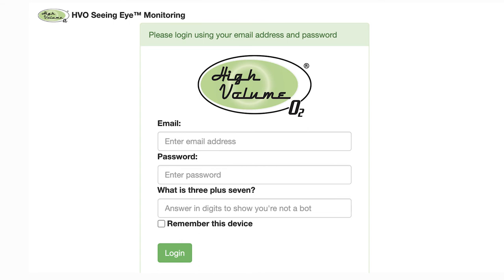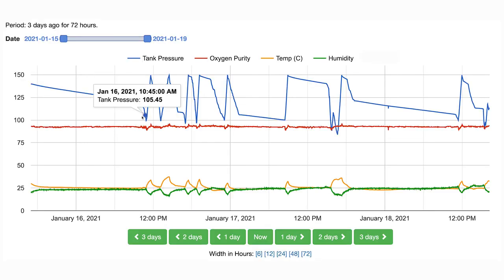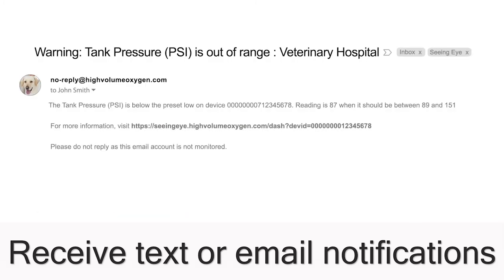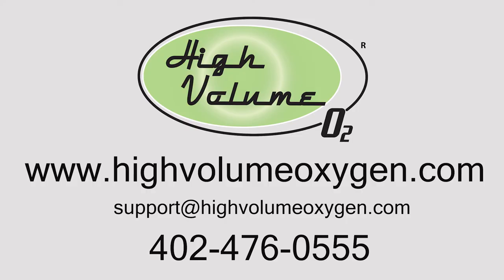Now you can use your registered email address to log into the HVO Seeing Eye cloud monitoring portal. Logging into the Seeing Eye portal will allow you to view a historical graph of your high-volume oxygen system's data for up to one year. The graph will display critical data such as tank pressure and oxygen purity, as well as diagnostic data such as temperature and humidity. You can set up text or email notifications to be sent if the metrics drop outside of a desired range. You can also remotely check in on your system. Congratulations! Your high-volume oxygen system is now installed. There's no need to turn the oxygen concentrators or HVO system off, as your oxygen production is now automated. If you have questions, visit our FAQ or support page, email us at support@highvolumeoxygen.com, or call 402-476-0555.